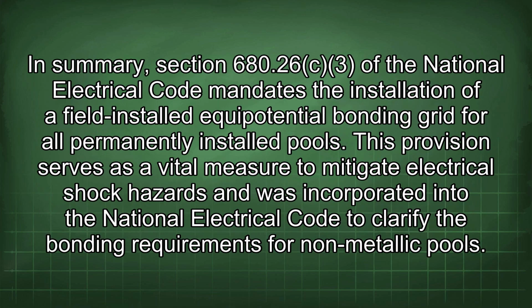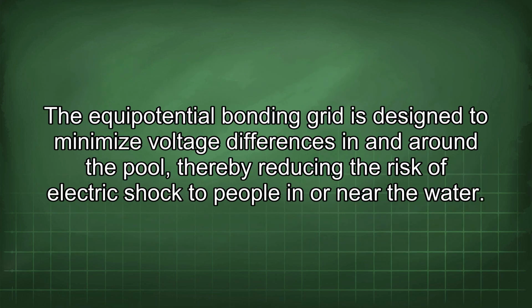In summary, Section 680.26(c)(3) of the National Electrical Code mandates the installation of a field-installed equipotential bonding grid for all permanently installed pools. This provision serves as a vital measure to mitigate electrical shock hazards and was incorporated into the National Electrical Code to clarify the bonding requirements for non-metallic pools. The equipotential bonding grid is designed to minimize voltage differences in and around the pool, thereby reducing the risk of electric shock to people in or near the water.